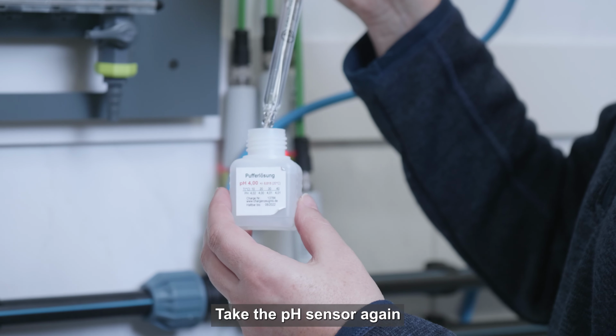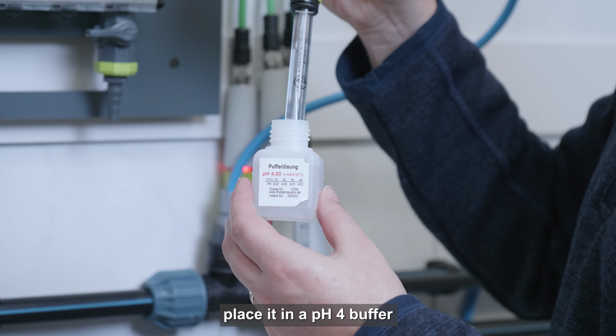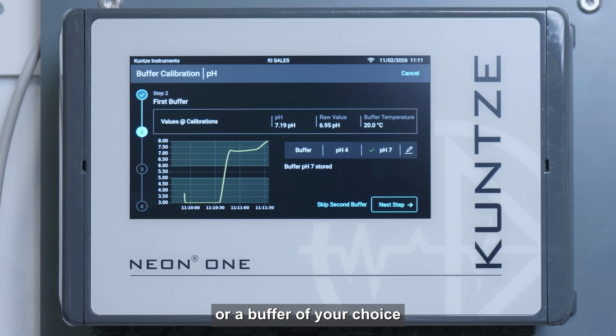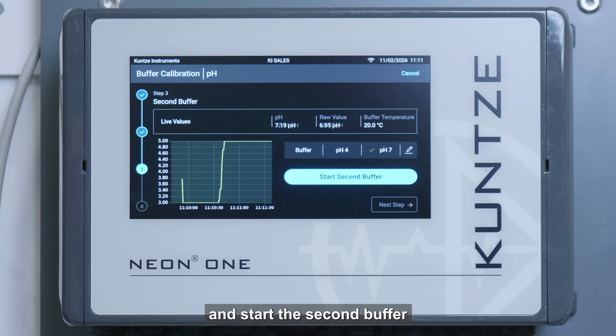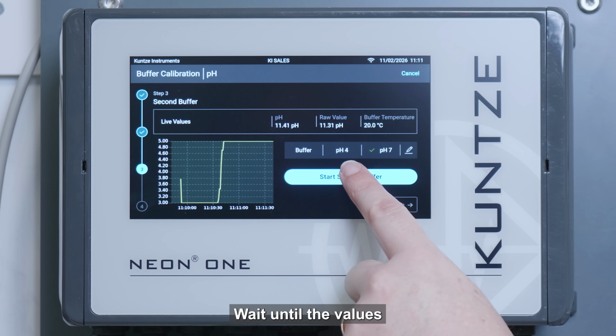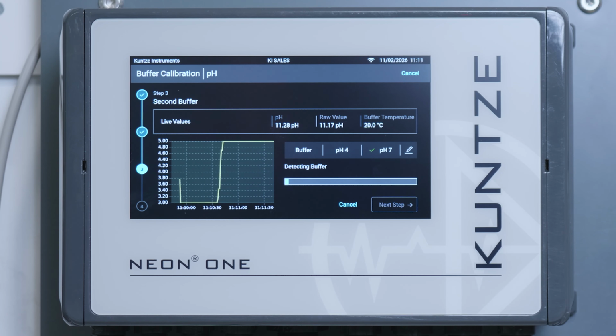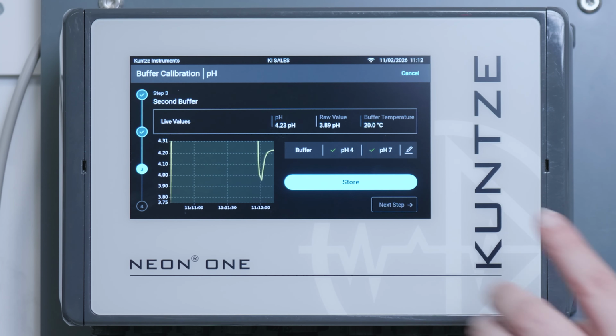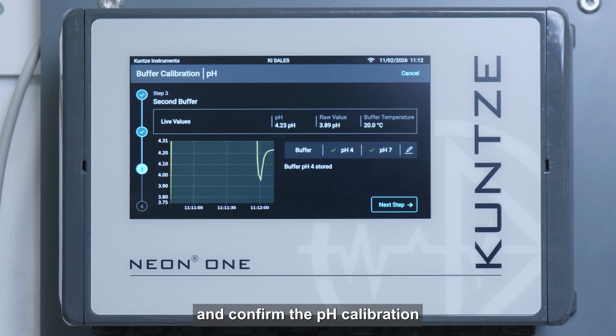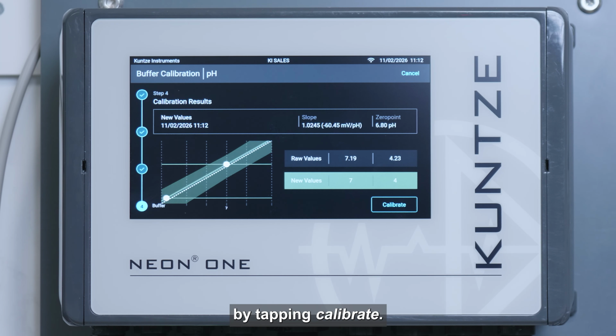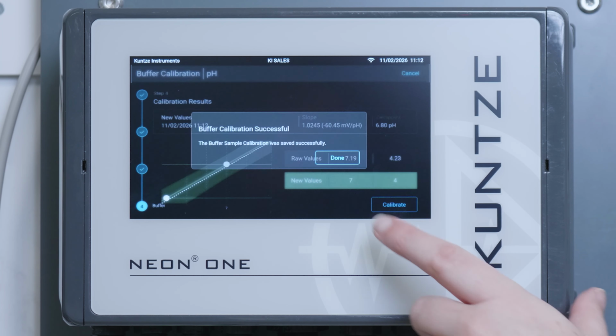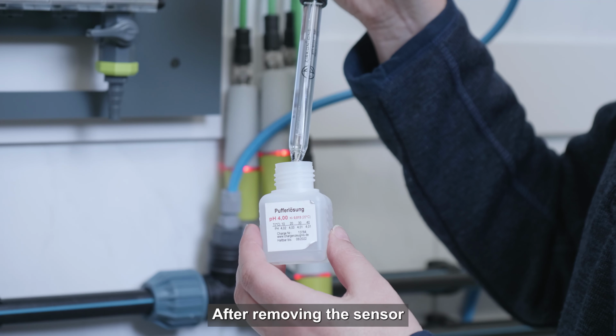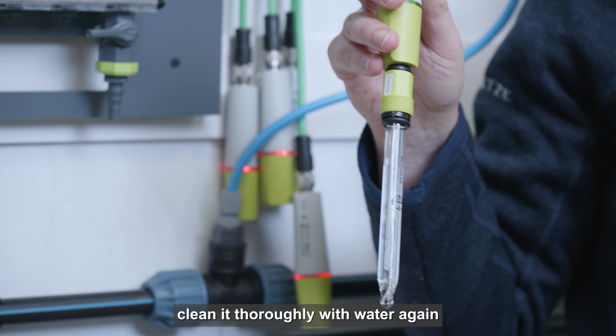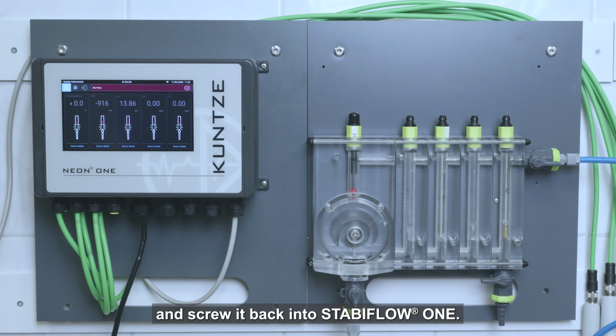Take the pH sensor again, and this time, place it in a pH 4 buffer, or a buffer of your choice, and start the second buffer on the Neon One. Wait until the values have been determined. Tap on Store and confirm the pH calibration by tapping Calibrate. After removing the sensor from the buffer, clean it thoroughly with water again and screw it back into StabiFlow 1.